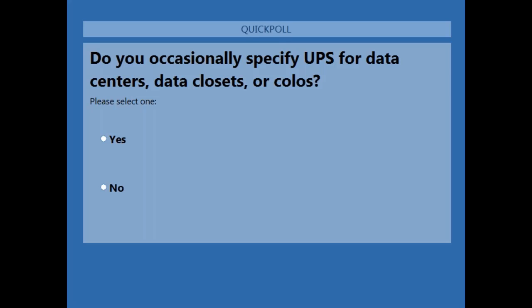Like I said, we see block redundant and distributed redundant approximately equally deployed. From day one it's not a problem, but I've heard several customers raise it as a concern because you never know what those crazy IT guys are going to do. You can add a lot of monitoring, like ABB offers monitoring for our power distribution as well. So you would have all the data. If you know the maximum current on each power line, we can monitor that and it can raise a flag.